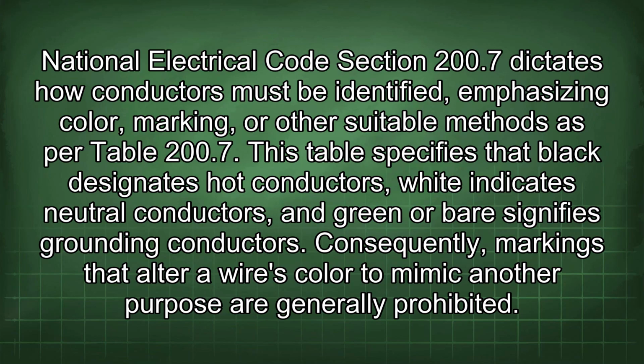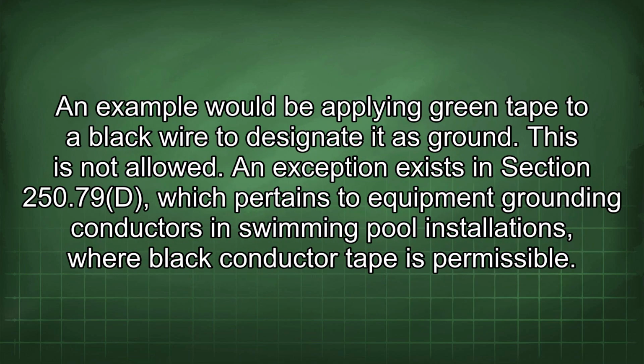National Electrical Code Section 200.7 dictates how conductors must be identified, emphasizing color, marking, or other suitable methods as per Table 200.7. This table specifies that black designates hot conductors, white indicates neutral conductors, and green or bare signifies grounding conductors. Consequently, markings that alter a wire's color to mimic another purpose are generally prohibited. An example would be applying green tape to a black wire to designate it as ground.